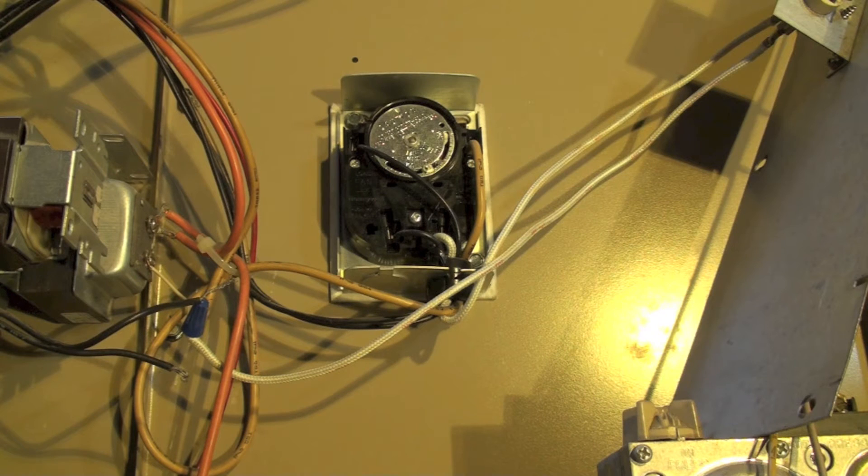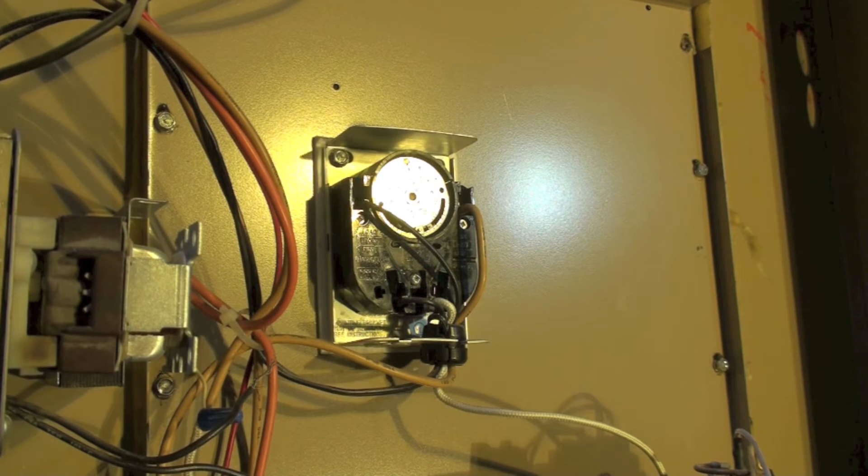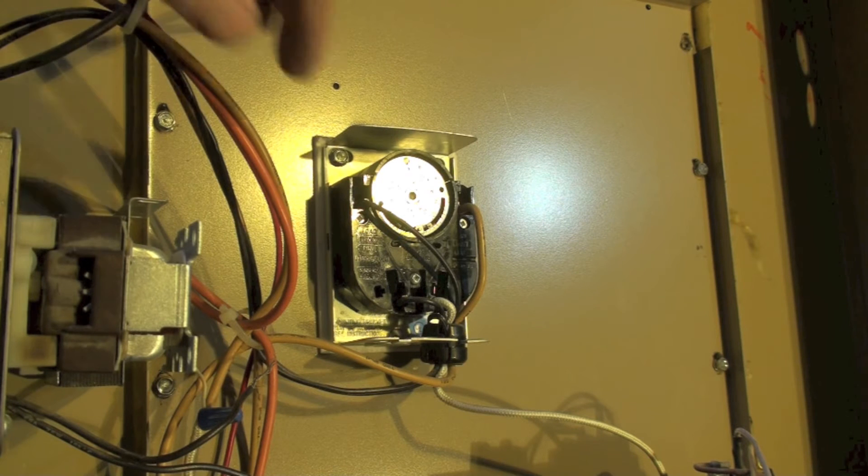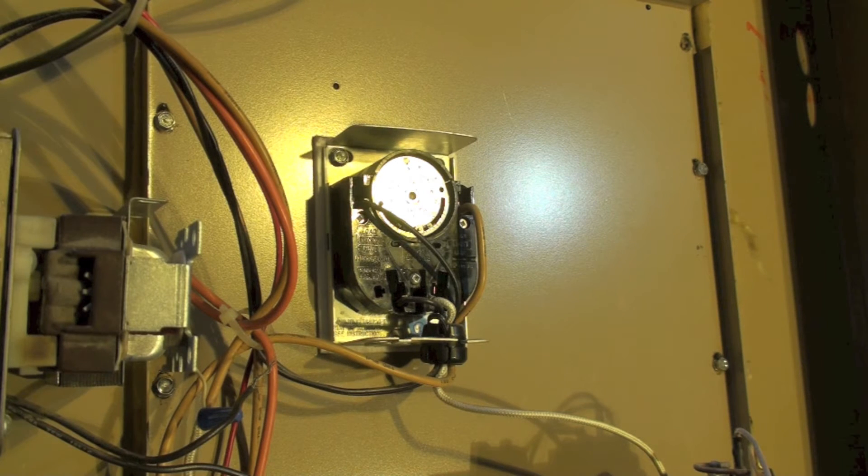This furnace also has two limits in that heat-operated fan switch. There is a limit switch that if for some reason the fan didn't come on or whatever, it had a plugged filter or so on, that will kick off if it overheats.